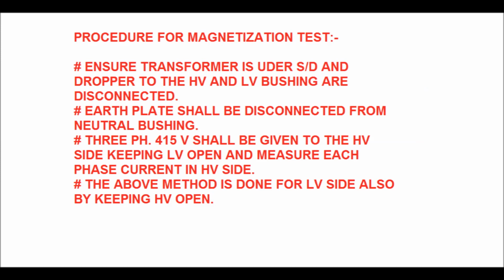Magnetization current test for a 3-phase power transformer. First, we have to ensure that the transformer is under complete shutdown and the droppers to the HV and LV bushings are disconnected. Number 2, the earth plate connected to the neutral bushing shall be disconnected from the neutral bushing. Number 3, a 3-phase supply should be connected to the HV side, keeping the LV side open, and measure each phase current in the HV side by clamp-on meter. The above method is also done for the LV side by keeping the HV side open and measuring the current in each phase by clamp-on meter.